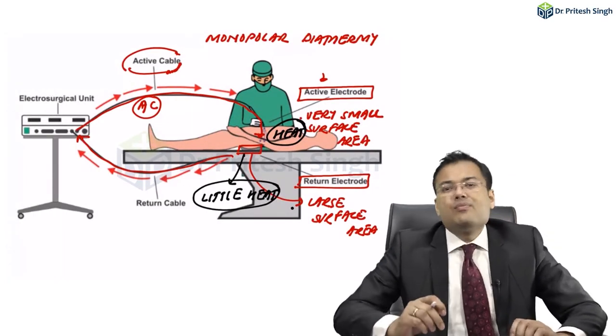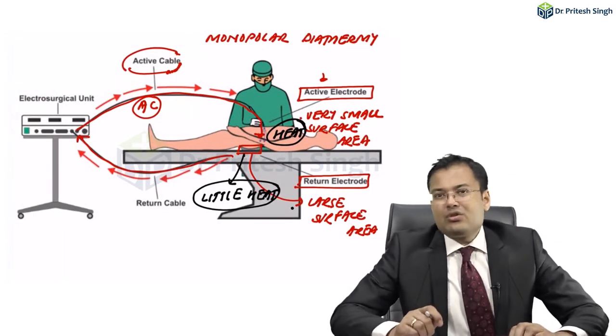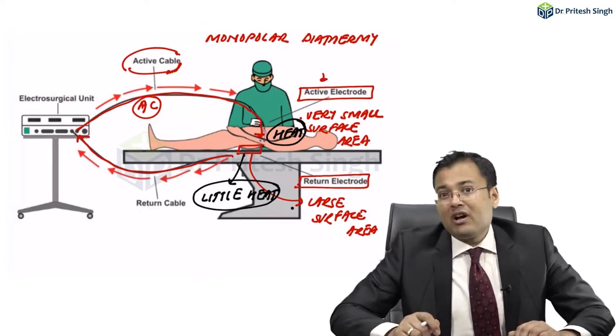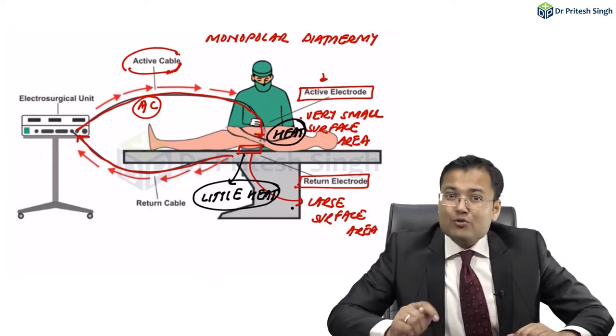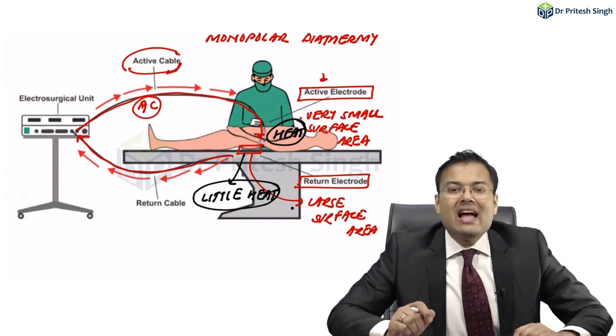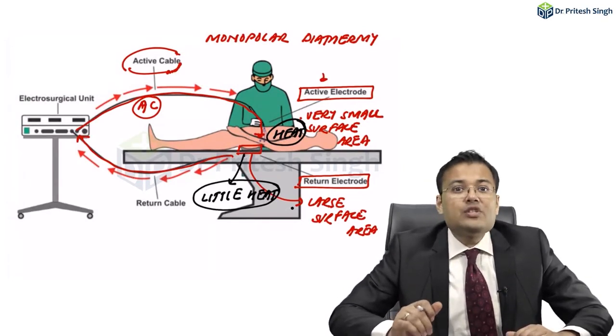The heat produced at the active electrode is responsible for denaturation of protein, and that is used for cutting and coagulation of the tissues.